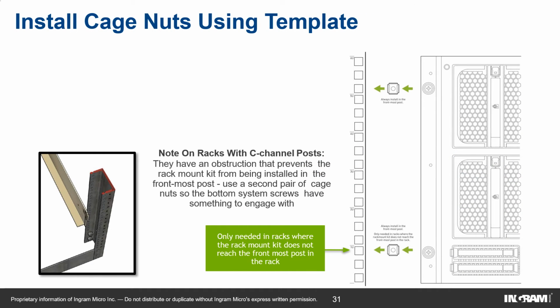So the next step would be to install the cage nuts. There is a template that is included as part of the rack kit, and it should be used to align the desired location of the system to where the included cage nuts have to be installed. These templates are double-sided, so they can be used as a reference on the left and the right post of the rack. Usually it is only needed in racks where the rack mount kit does not reach the frontmost post in the rack.